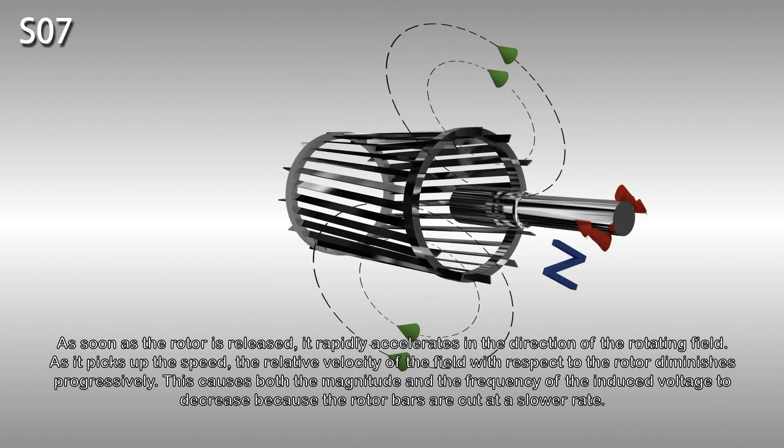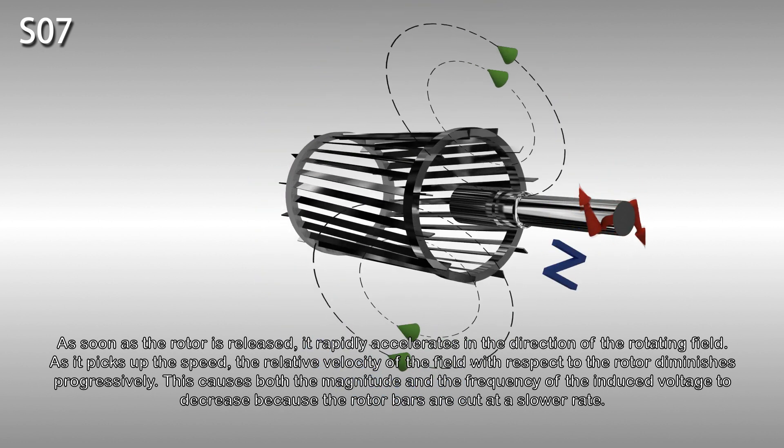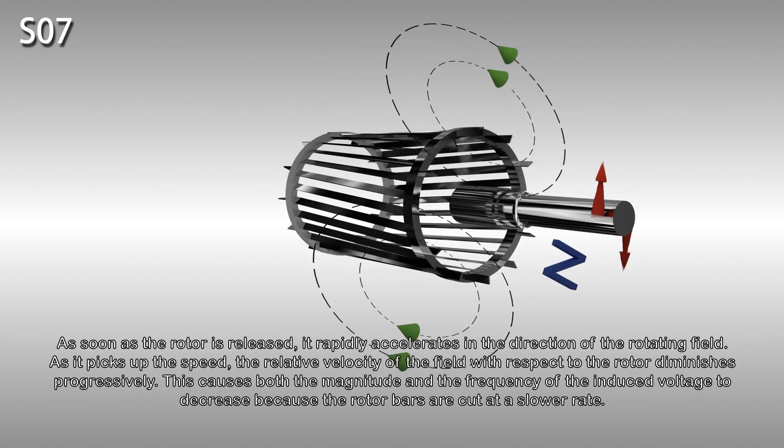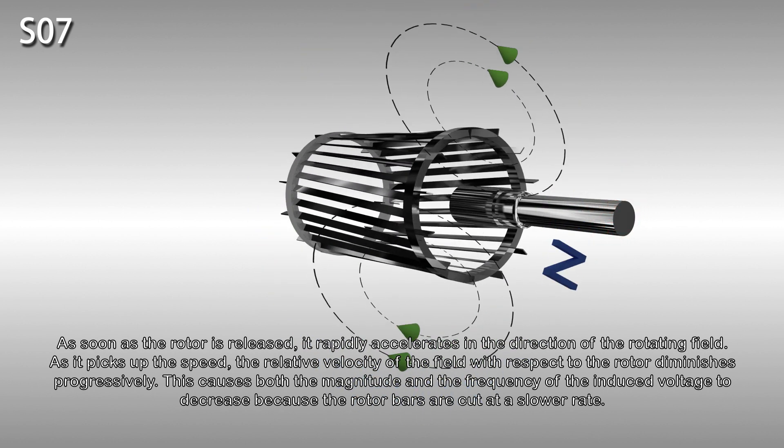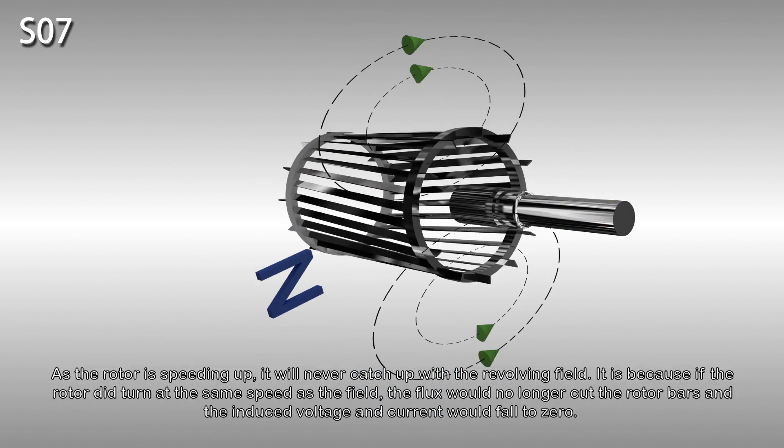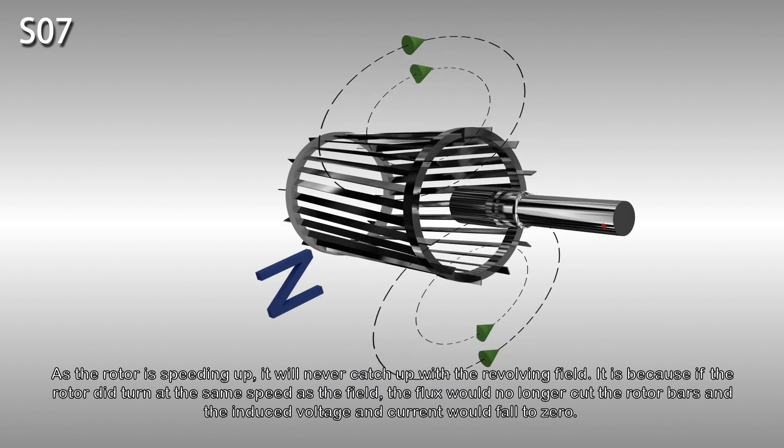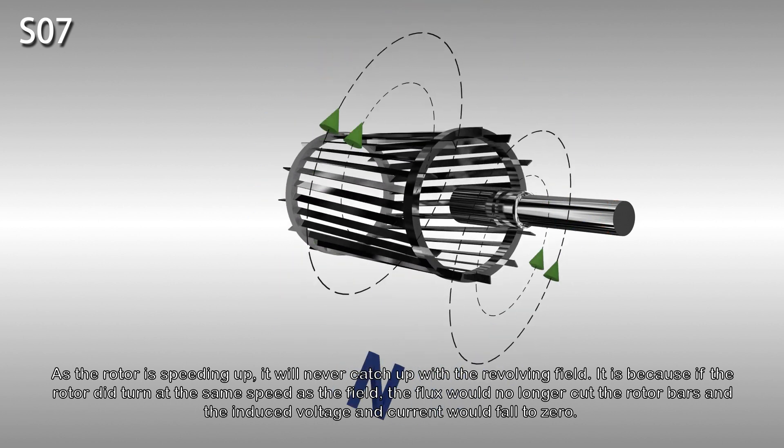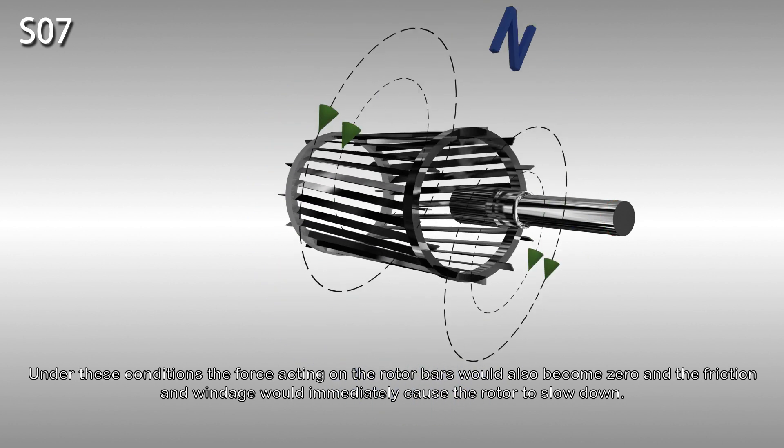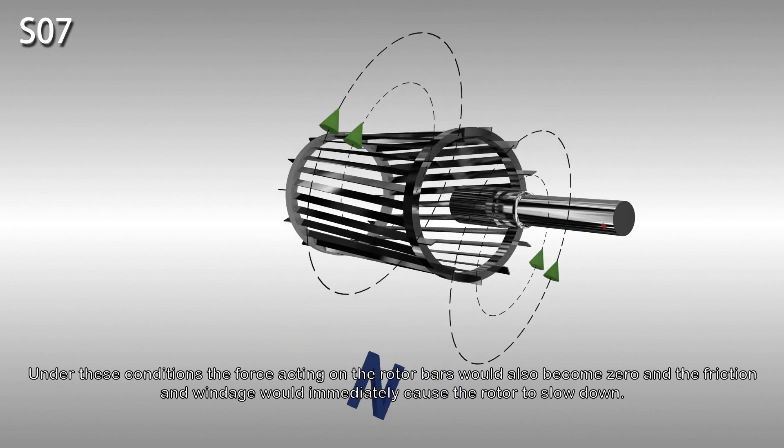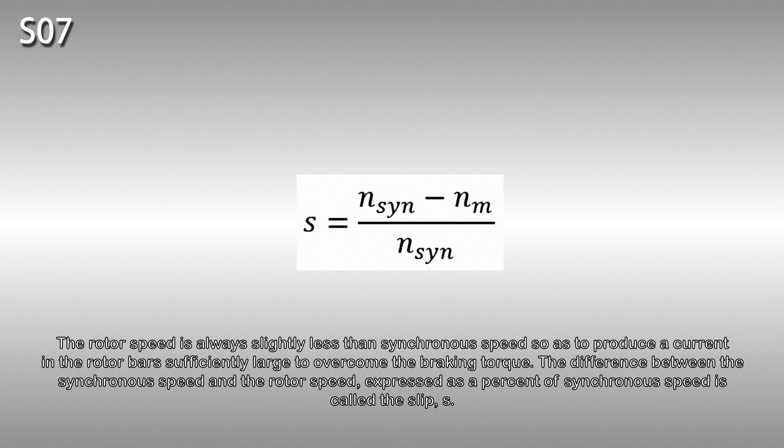As it picks up speed, the relative velocity of the field with respect to the rotor diminishes progressively. This causes both the magnitude and the frequency of the induced voltage to decrease because the rotor bars are cut at a slower rate. As the rotor speeds up, it never manages to catch up with the revolving field. If the rotor did turn at the same speed as the field, the flux would no longer cut the rotor bars and the induced voltage and current would fall to zero. Under these conditions, the force acting on the rotor bars would also become zero and friction and windage would immediately cause the rotor to slow down. The rotor speed is always slightly less than the synchronous speed in order to produce a current in the rotor bars sufficiently large enough to overcome the braking torque. The difference between the synchronous speed and the rotor speed, expressed as a percentage of synchronous speed, is called the slip S.